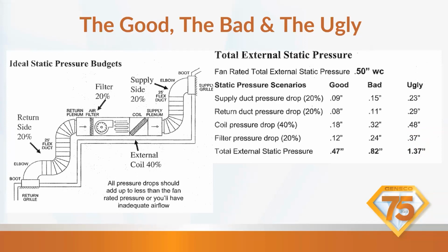And so when does it fail? When you need it the most, right? Deepest winter or the hottest days, that thing's going to fail on you. And it's because of your static airflow. So that has to be addressed, whether it be a bigger filter, bigger return air, adding a return air. It could be on the supply side. Homeowner has shut off a bunch of registers to save money on that side of the house.